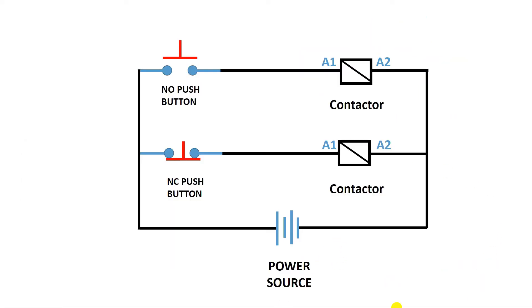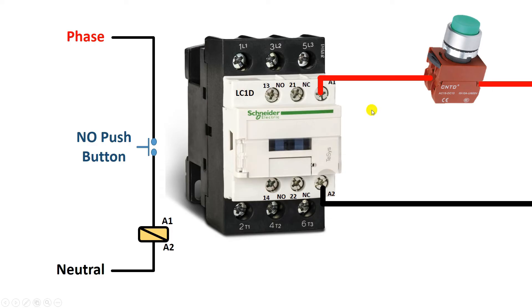Now let's move forward. In the last class, I told you that through this push button we turn on and off the contactor. Now I didn't tell you what happens in the contactor when a NO push button is connected, or what happens when an NC push button is connected. To explain this, first I will connect this contactor through a NO push button. For this connection, I made a symbol here. At A2 terminal of this contactor, neutral power supply is directly connected.